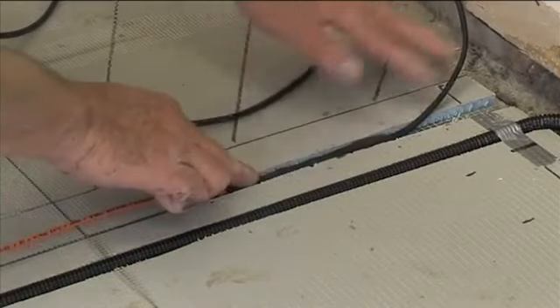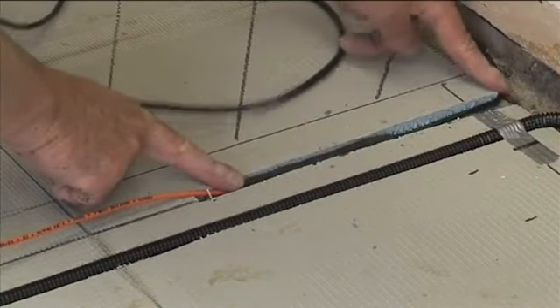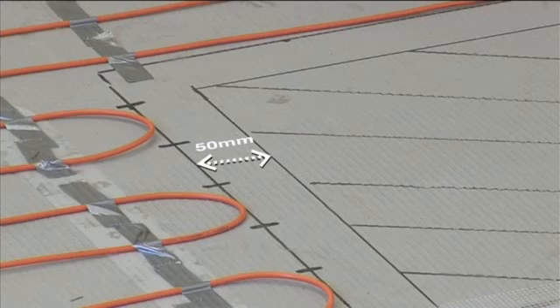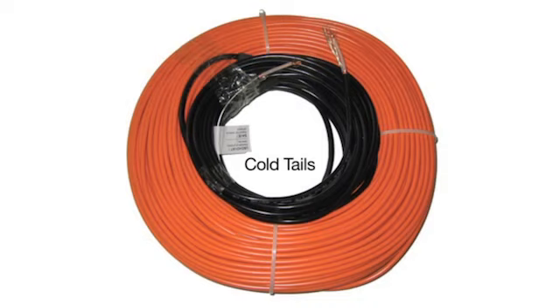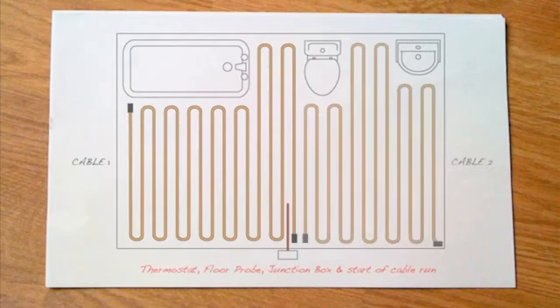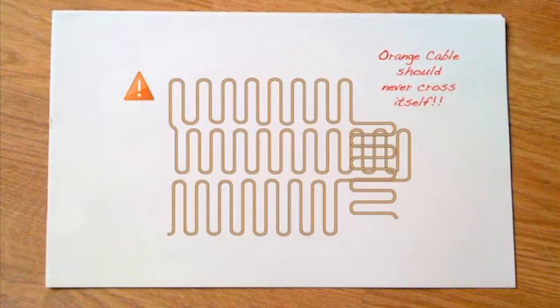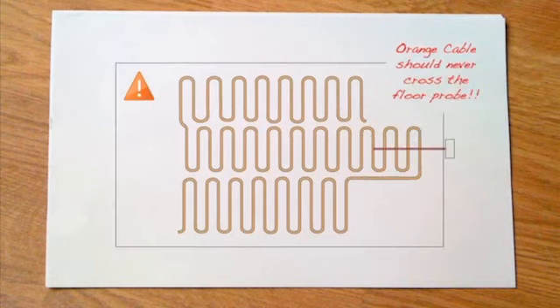The ECOflex cable cold tail is 3 meters long. Cable spacing and perimeter wall clearance must be a minimum of 50 millimeters. Plan your installation so that all cable cold tails, the black power cables, terminate in one junction box. Multiple cables are joined in parallel. The orange heating cable should never cross at any point. Heating cables should never cross over the floor probe.